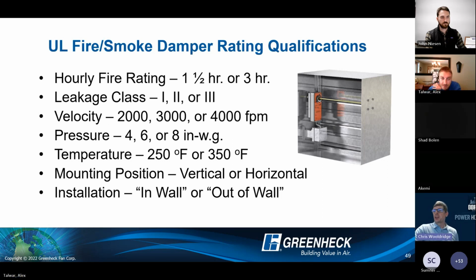Yes, go ahead. We got a couple of questions. Well, one real quick. Why would you need a modulating damper? Really, the only need for modulating dampers is if you're trying to combine the functionality of a modulating volume control damper into your fire smoke damper. So it's kind of the Cadillac of dampers. You got every possible functionality. Yeah, it's a volume control application built into the fire smoke environment, basically.